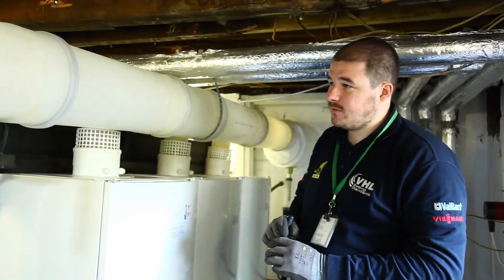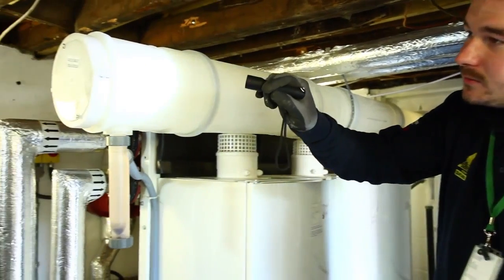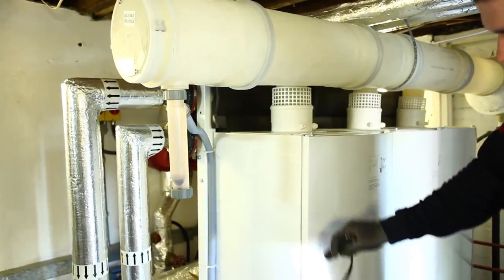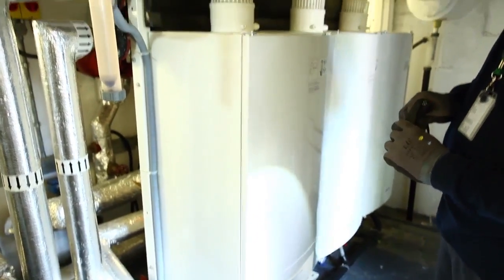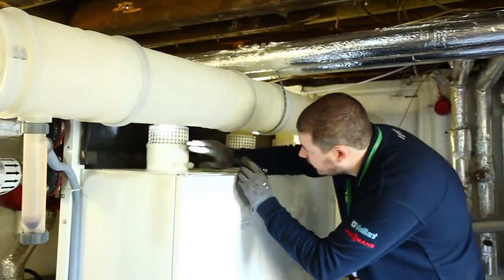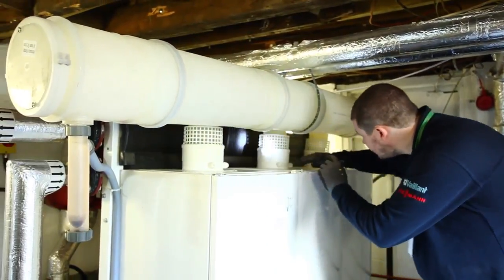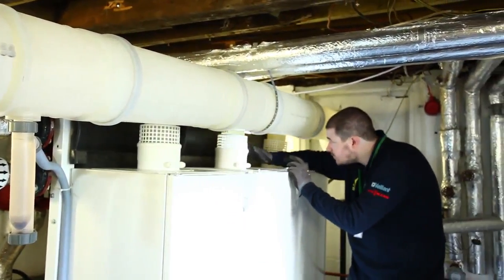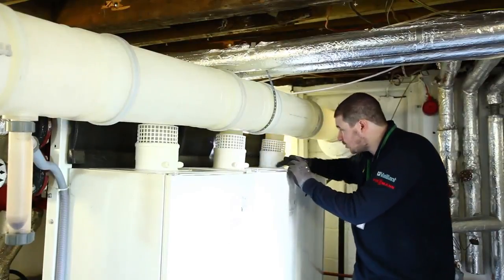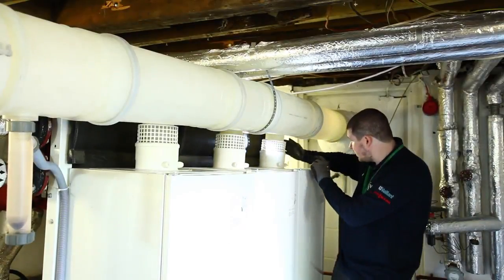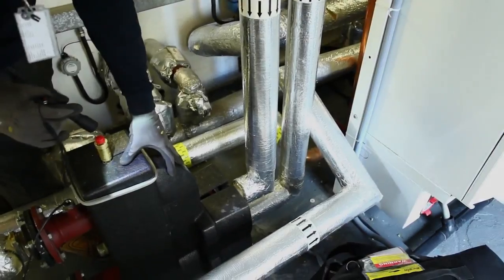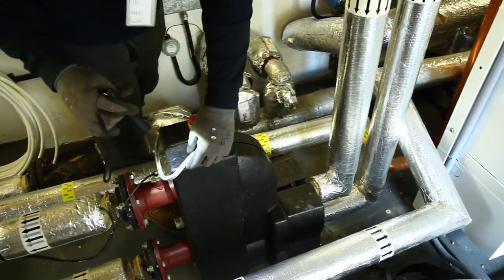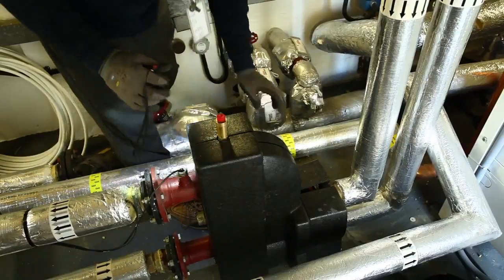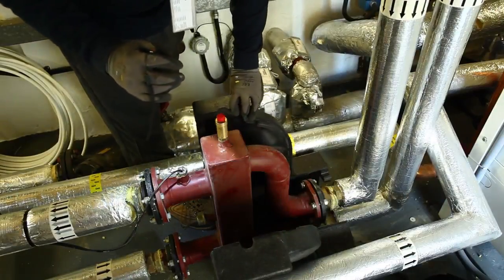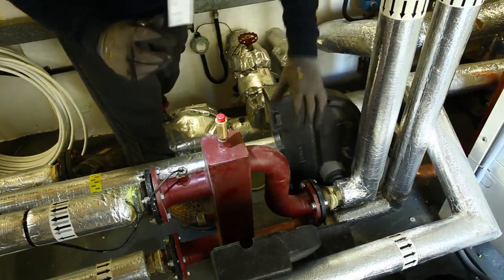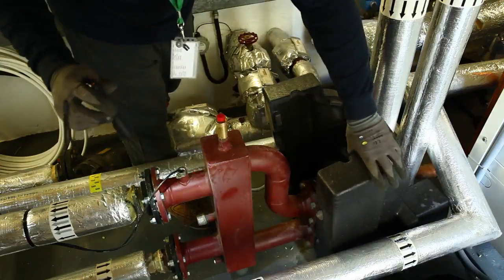Right, just inspecting the flues, check the condition of them, make sure there's no leaks, and it's all working without any hesitation. The other thing we inspect is the air intakes on all the boilers to make sure there's no dust, no foreign debris going down the boilers which will cause the boilers to work incorrectly. The header is part of the installation which protects the boiler from thermal shock and any foreign material going back into the boiler. I'll just remove the insulation so you can see.